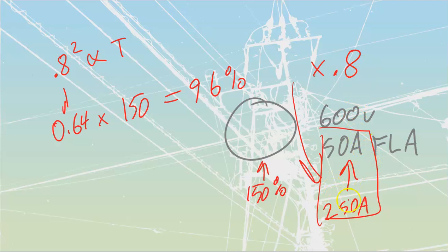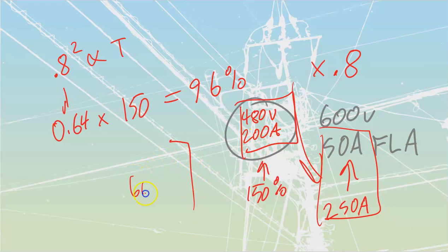Because this motor is reduced through that autotransformer, we also have an additional compounding on my high side, right? If the motor itself is receiving 200 amps, and it's operating at 80% voltage, that's going to be 480 volts. That 200 amps that we are delivering out at the 80% voltage is also going to be transformed up through the high side, right? This is the low side over here. The high side is still going to be 600 volts.